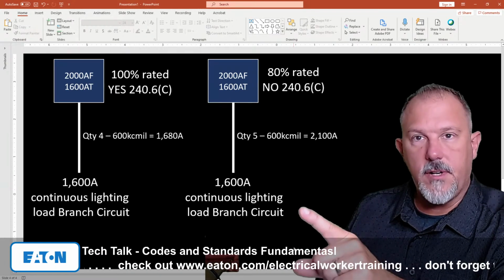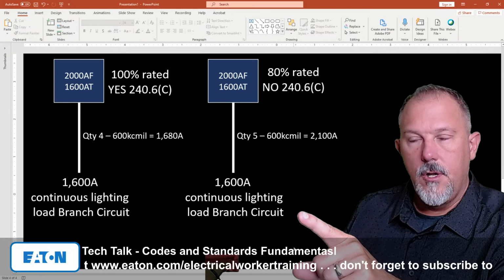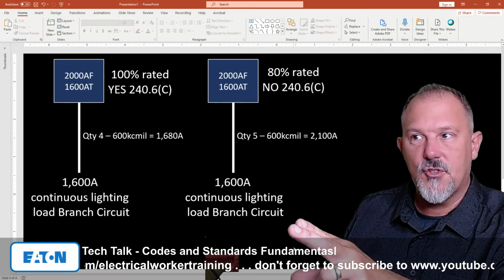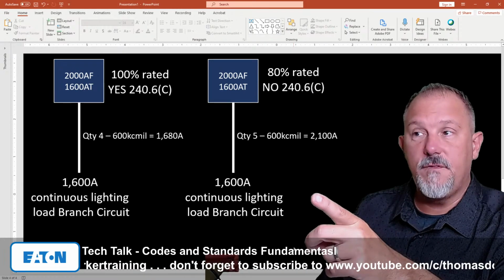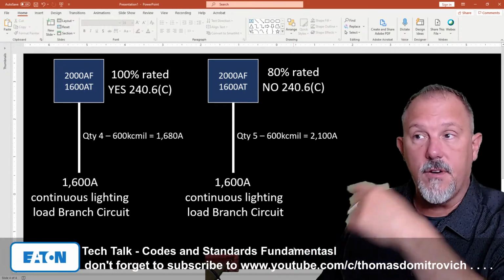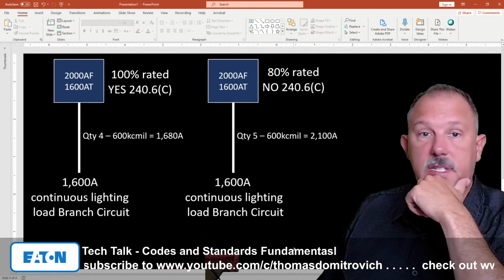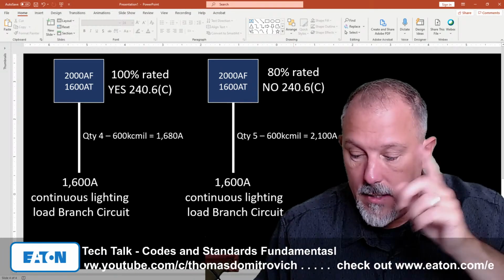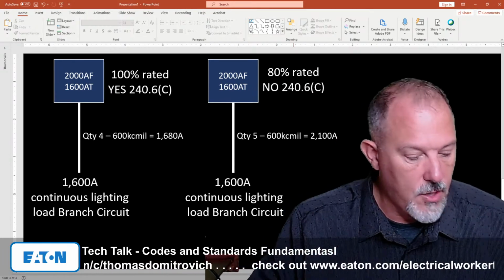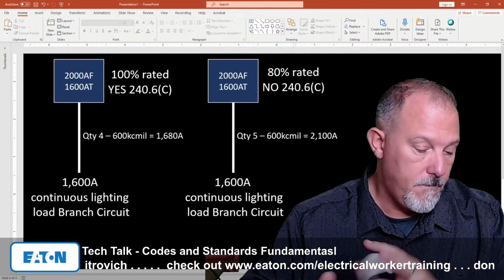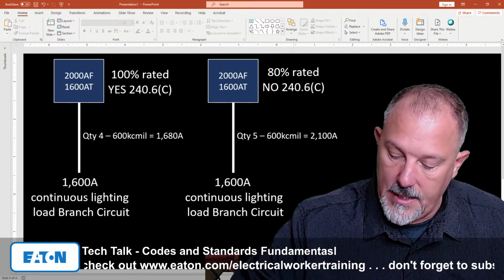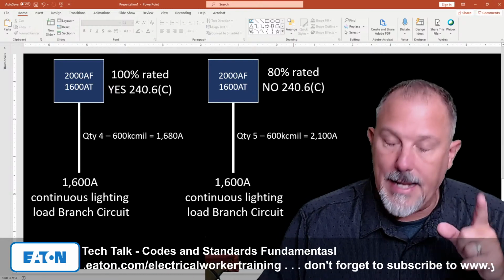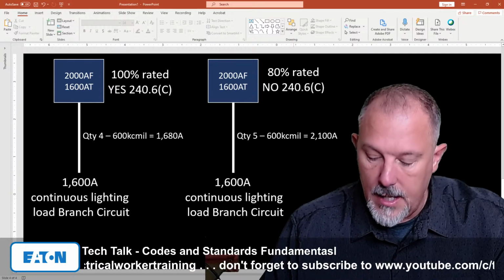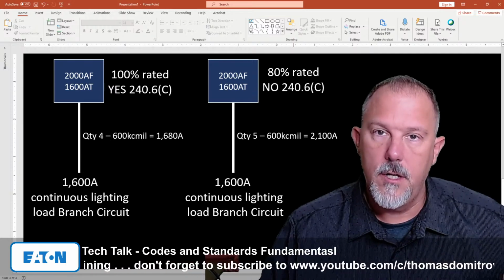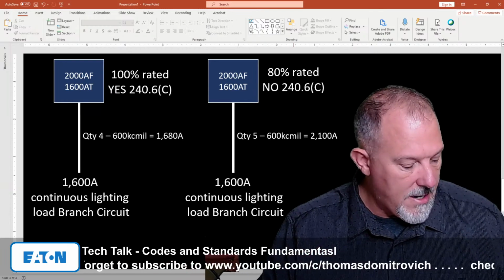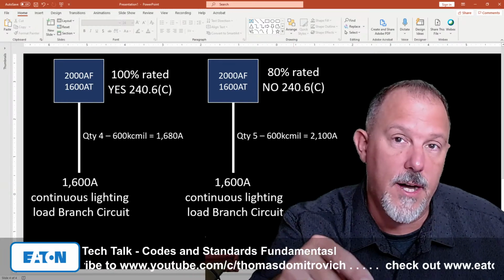with four 600 kcmil conductors on a 2000 amp frame breaker at 1600 amp trip, meeting the requirements of 240.6(C), meaning you're locking the cover, or you've got the password protection, or it's in a locked room, etc. Now, let's take a look. Does this apply to feeders? So if we go to 215, 215.2, minimum rating and size, aligns with 210.19. 215.3 aligns with 210.20(A).